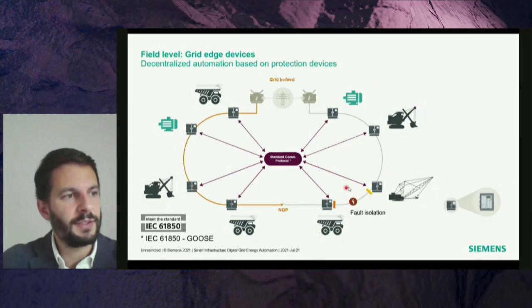So we have two open points to isolate that section, and finally we can restore power supply to the non-affected grid areas or loop sections. You can see my system can still operate. On average, the system runs the whole loop automation in less than 300, 200 milliseconds, depending on project-specific details. But at the end, my motivation is to isolate the loop as fast as possible while still being able to operate the remaining areas of my installation. That's in essence the concept of decentralized automation.